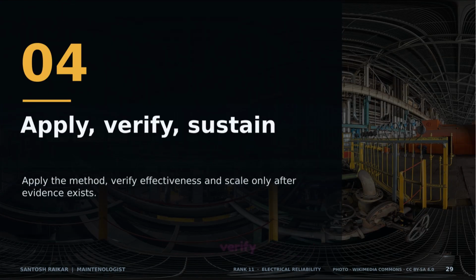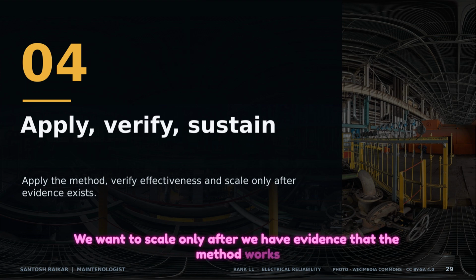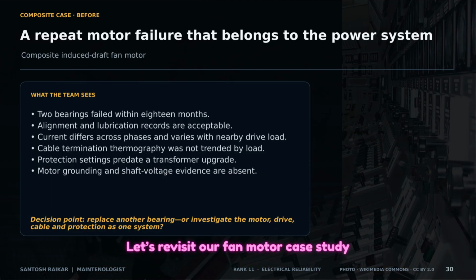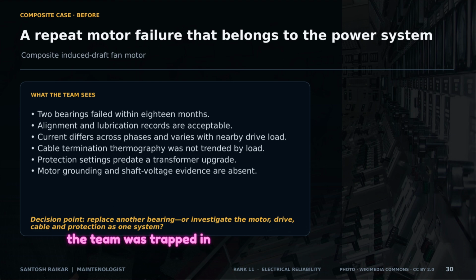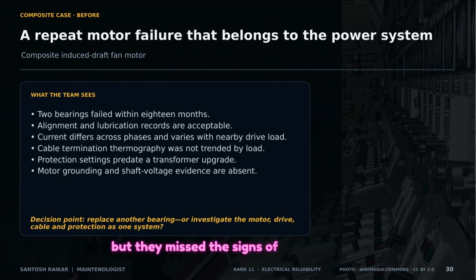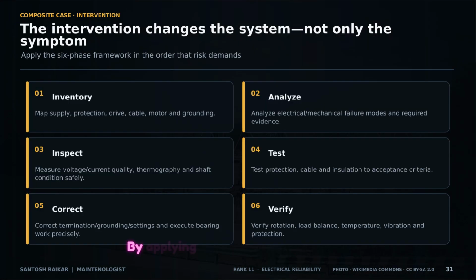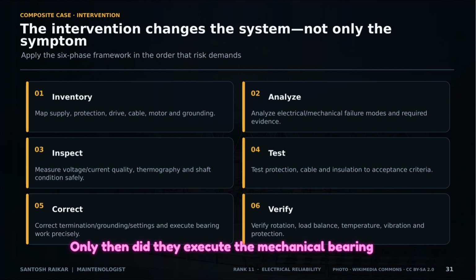Finally, we focus on how to apply, verify, and sustain these changes. We want to scale only after we have evidence that the method works. Let's revisit our fan motor case study. Before the intervention, the team was trapped in a cycle of bearing failures every 18 months. They were looking at the symptom, but they missed the signs of phase current imbalance and outdated protection settings. They faced a choice: replace another bearing or investigate the entire system. By applying the Power 6 framework, the intervention shifted from the symptom to the system. They mapped the supply, measured the power quality safely, tested the insulation, and corrected the grounding. Only then did they execute the mechanical bearing work.